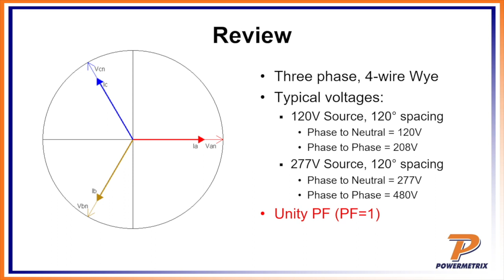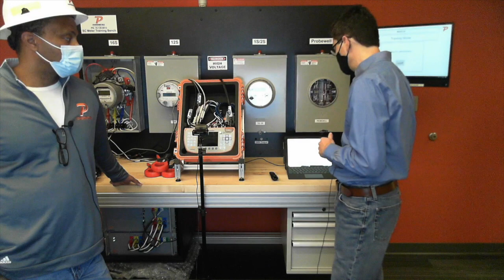Now, also on a self-contained meter, you've got a class, and they call it CL on the meter here. That's talking about the max current this meter can handle. So this is an example of a 2S meter, it's a class 200, CL 200, similar to a 16S. So you've got a selection between a class 200 or a class 320.